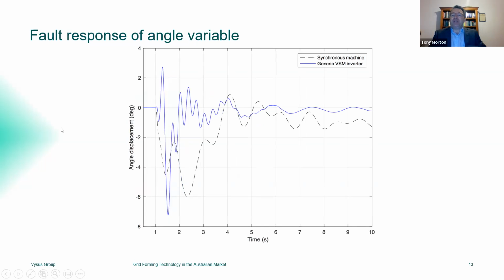We can also see, though, that if we look at voltage phase angles in the network and the displacement in those on recovery from the fault, we can see how these angles move around in the original system with a synchronous machine, and we can likewise see how they move around when we replace that with a grid forming inverter. And by and large, we see fairly similar stability characteristics as long as we have the control system tuned appropriately. So we can actually replicate the stabilising behaviour of the machine with things like virtual stabilising torque and so on with the power electronic plant.